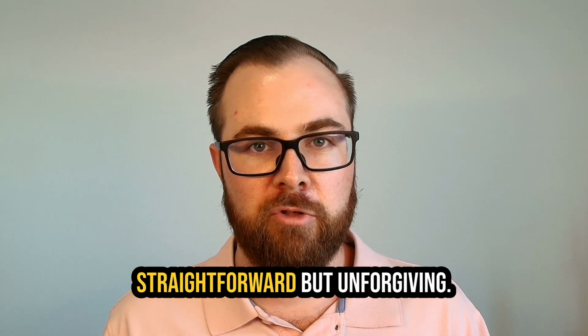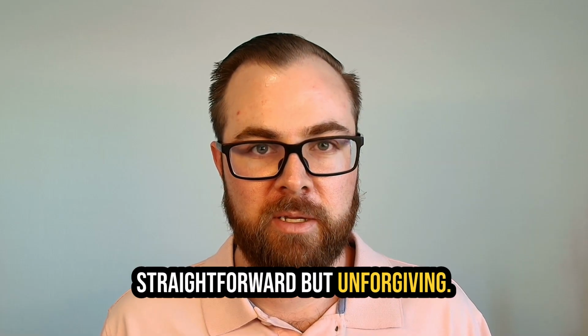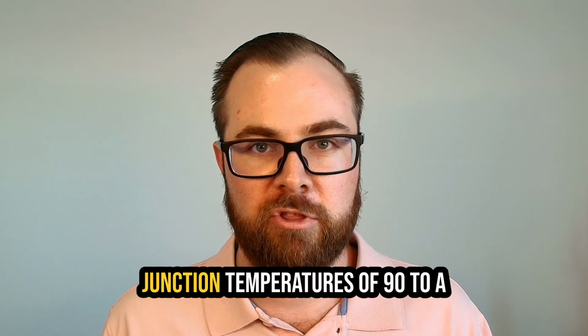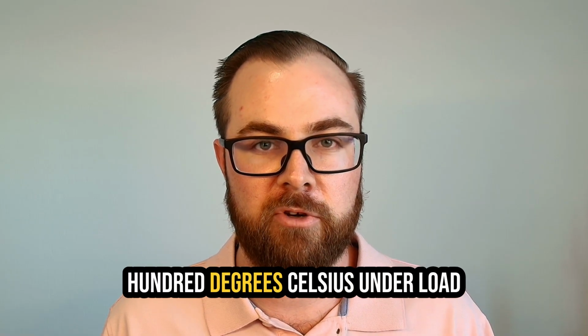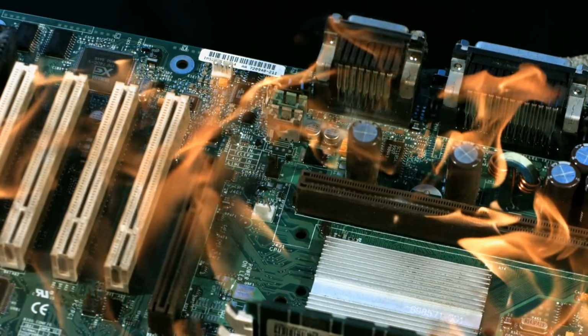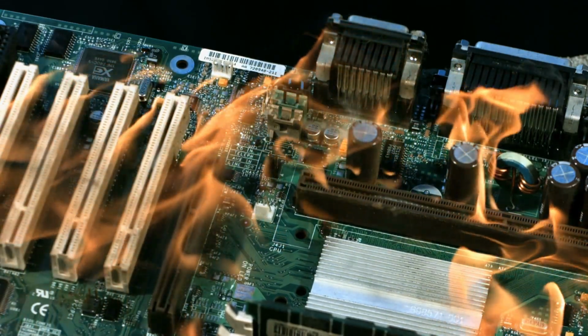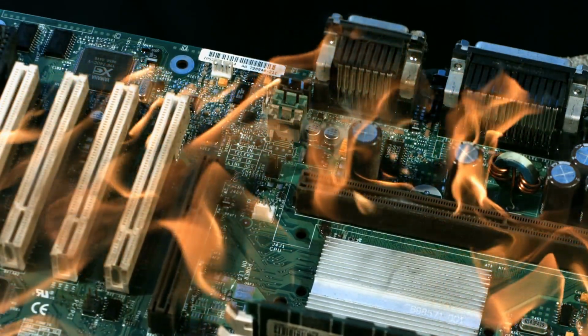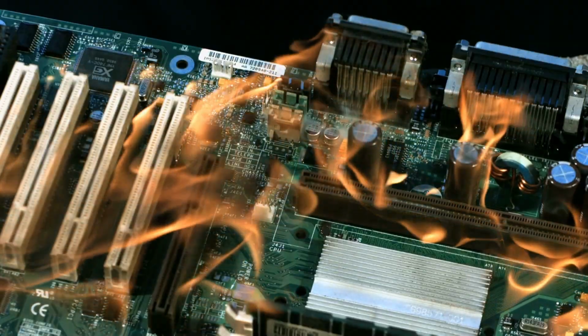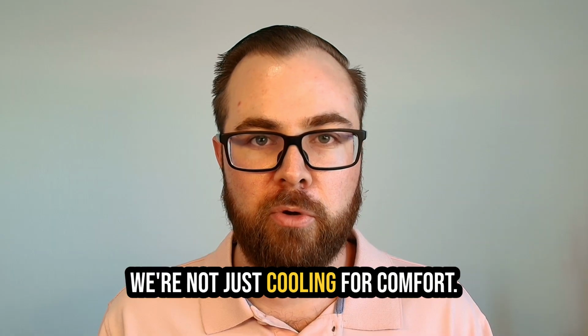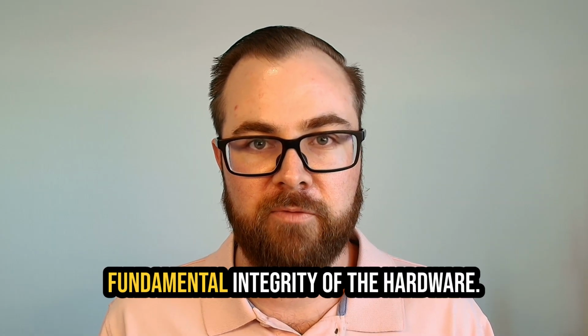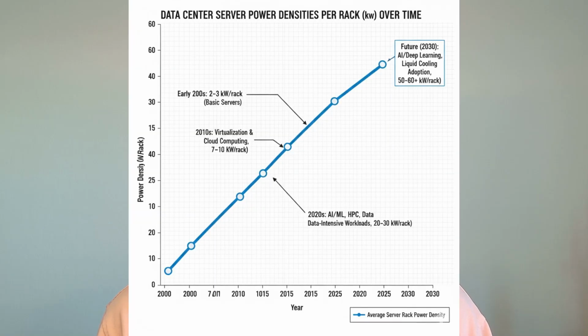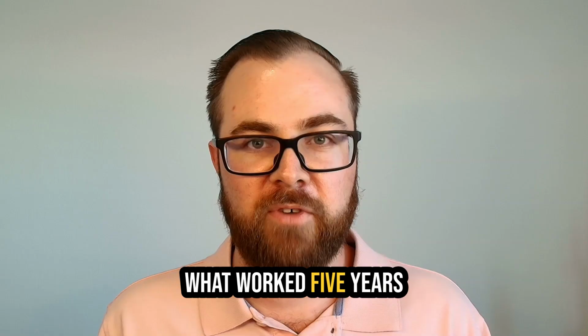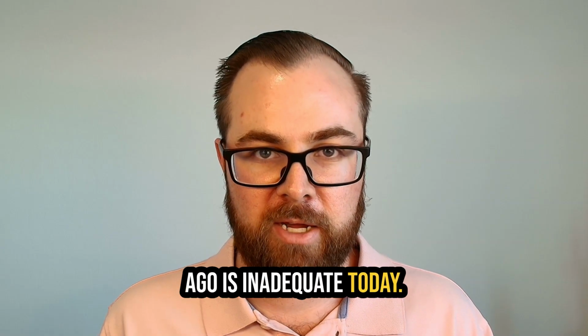The physics here are straightforward but unforgiving. Modern processors can reach junction temperatures of 90 to 100 degrees Celsius under load. At these temperatures, silicon degrades faster, solder joints weaken, and the risk of thermal runaway increases exponentially. We're not just cooling for comfort, we're cooling to maintain the fundamental integrity of the hardware. And with server densities increasing year over year, the challenge only intensifies. What worked 5 years ago is inadequate today.